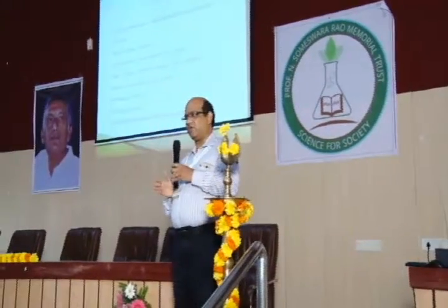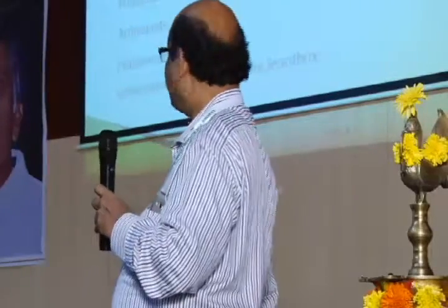So we have to see the daily BOD. The BOD, N and P ratio is very, very important. It is 100:5:1 or 100:5:2, depending upon different rates, generally 100:5. So what is the BOD organic load, what is the nitrogen, what is the phosphorus is very important. That is the first fundamental principle we have to see, even though the ETP is there.